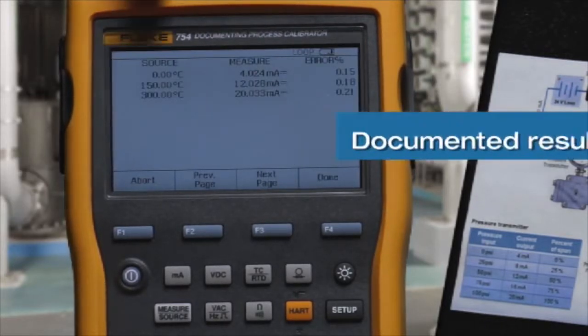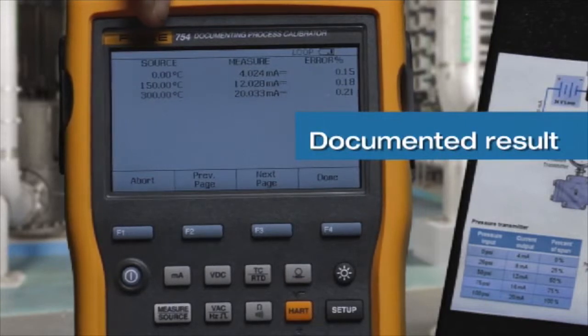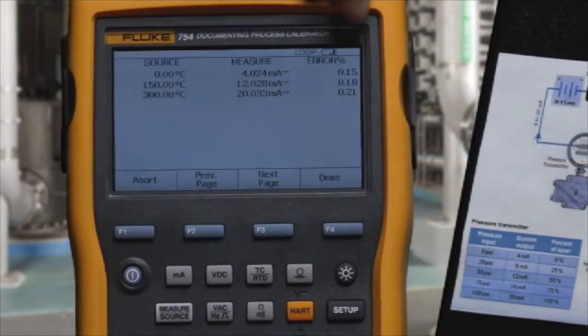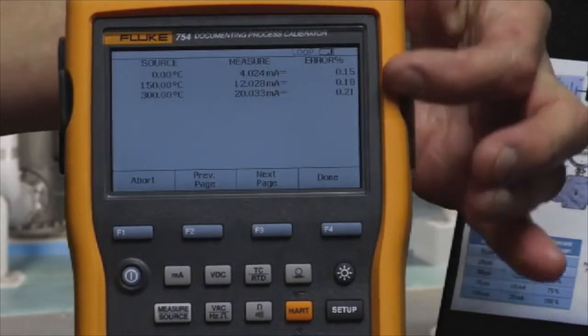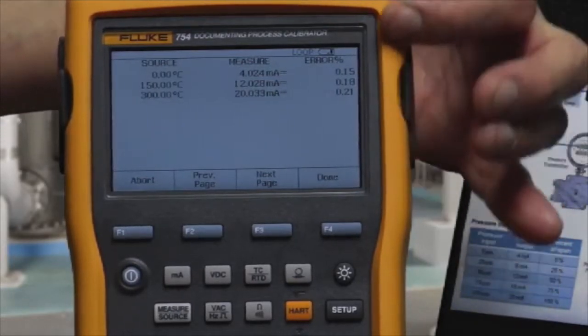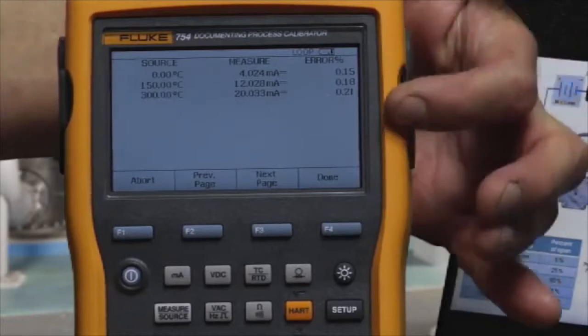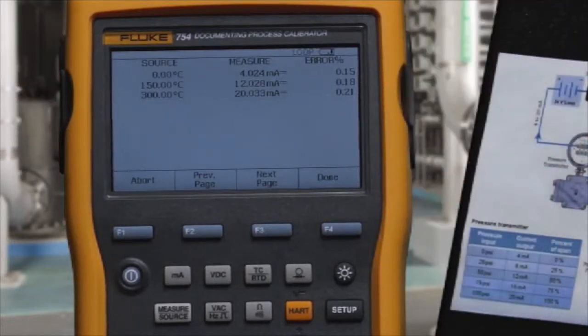When the test is done, you have the documented applied temperature, measured current, and error percent of span for each point. None of the error percents are in reverse video indicating that all the milliamp measured values are within the allowable test tolerance, and the transmitter passes the calibration test.